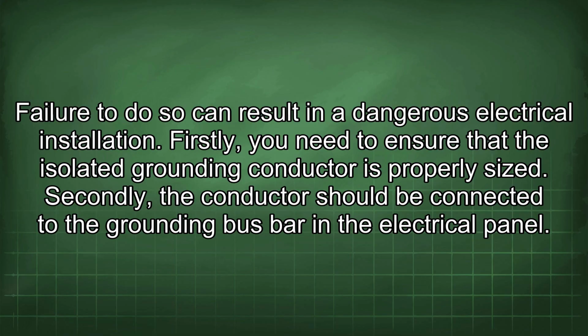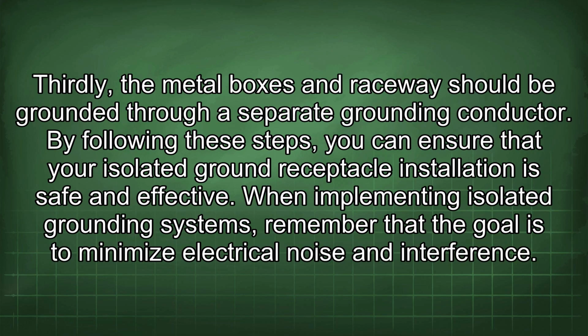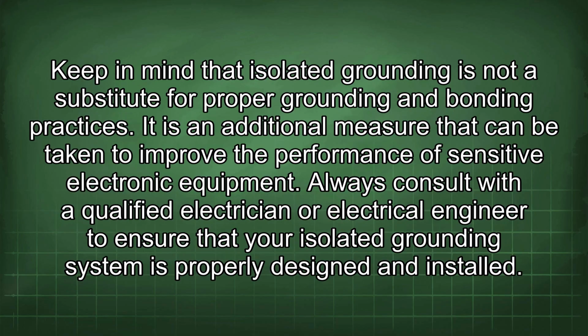Firstly, you need to ensure that the isolated grounding conductor is properly sized. Secondly, the conductor should be connected to the grounding bus bar in the electrical panel. Thirdly, the metal boxes and raceway should be grounded through a separate grounding conductor. By following these steps, you can ensure that your isolated ground receptacle installation is safe and effective. When implementing isolated grounding systems, remember that the goal is to minimize electrical noise and interference. Keep in mind that isolated grounding is not a substitute for proper grounding and bonding practices. It is an additional measure that can be taken to improve the performance of sensitive electronic equipment.